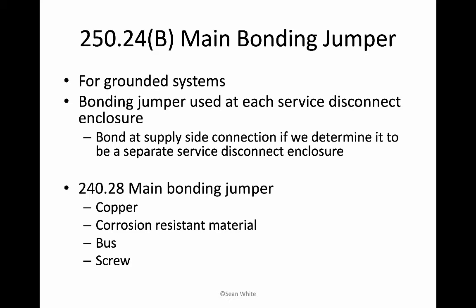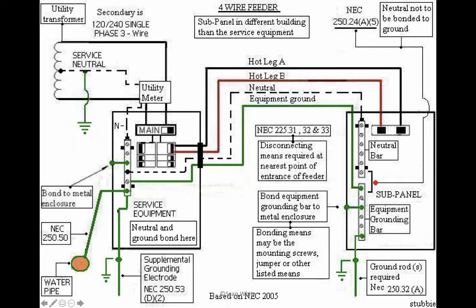That's your single point of system grounding, and that's your main bonding jumper. And now on the DC side of the inverter, we don't do that. If you were going back to the 2014 NEC, our main bonding jumper was considered to be a fuse inside the inverter, or sometimes it would be a circuit breaker. There we go, review. Main bonding jumper in the main service panel, your single point of system grounding. But if you were over on the other side of the main breaker, if you're doing a supply side connection on the other side of the main breaker, there's different theories on if you can bond it here separately or over here.